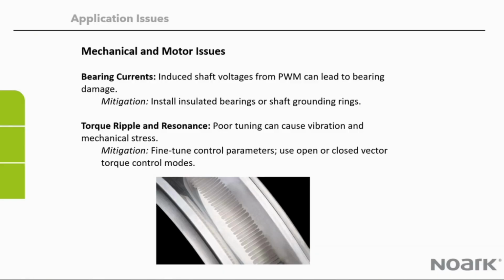Mechanical and motor issues. You end up with bearing currents and torque ripple and resonance. You can have shaft voltages, which could damage your bearings, and the general recommendation would be to install insulated bearings or grounding rings. For torque ripple and resonance, you could end up causing vibration and mechanical stress due to poor tuning. Fine-tune your control parameters and use open and closed loop torque control techniques.